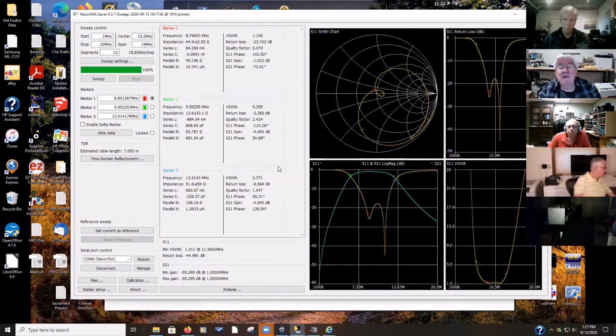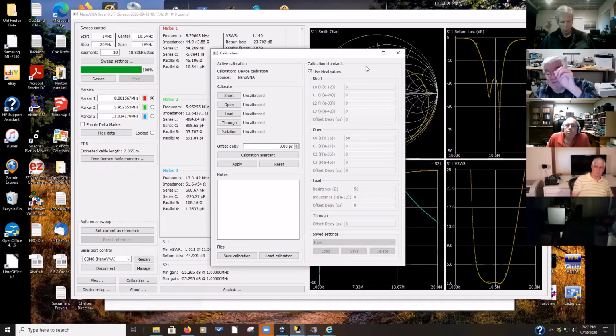Can you explain the ideal values? Oh, sure. Let me go back to calibration. Now, this is from my reading, not from personal experience. Ideal values are the ideal values that the perfect analyzer can be calibrated to. They're probably a fairly good ways away from practical or the normals. But some of these values here, if this was calibrated and set on here, you can see that the units here, we're talking femtofarads, like a 10 to the minus 15 or something like that. And so they're pretty minute values.